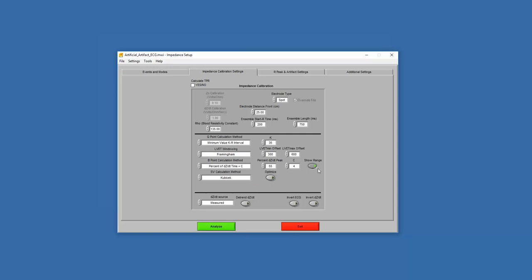The 'Show Range' option displays the high and low bounds where we expect the B notch to end up. If you didn't want to see that in your analysis, you could turn it off, but normally it's helpful to keep it on. We also have 'Invert ECG' and 'Invert dz/dt' options. Inverting dz/dt is only likely needed if you're bringing in a file from a different system — ours should always be positive. For Invert ECG: in older applications we'd ask you every single time whether it was inverted, but now you can just click this once and it'll ensure they're all inverted for you.